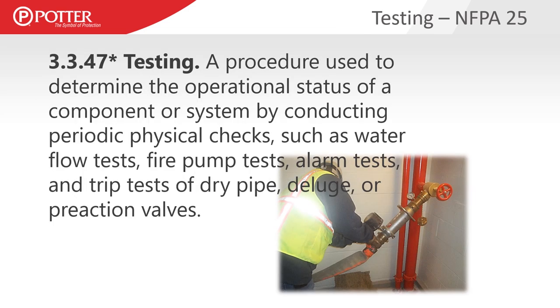NFPA 25 also defines the term testing. Now we're into a procedure — this is a procedure used to determine the operational status of some of these components. The main difference between a test and an inspection is that now we're operating the device to ensure it's working properly. There's an asterisk beside definition 3.3.47, indicating annex language with explanatory information noting that a test becomes more valuable when we compare the data to that of a previous test.